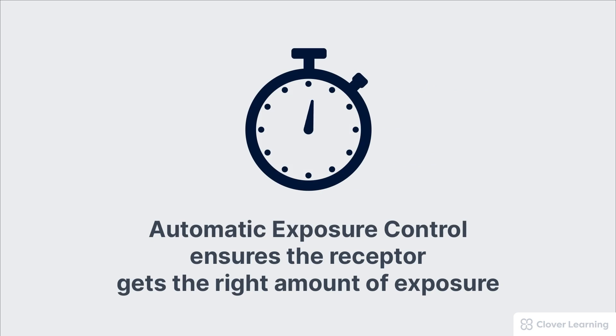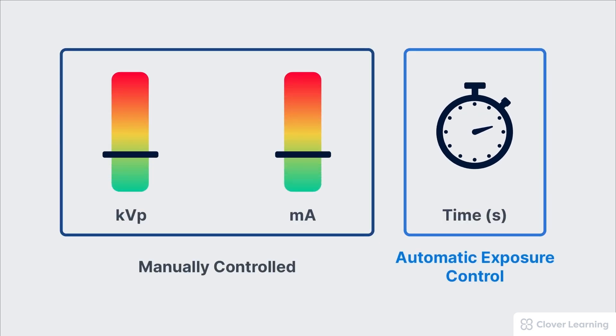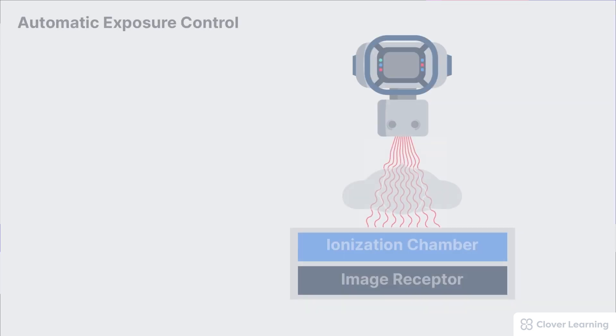The name automatic exposure control tells us exactly what it does — it makes sure the receptor gets exactly the right amount of exposure. During a procedure, the kVp and the mA are set by the operator, but the AEC system sets the exposure time and therefore controls the total mAs.